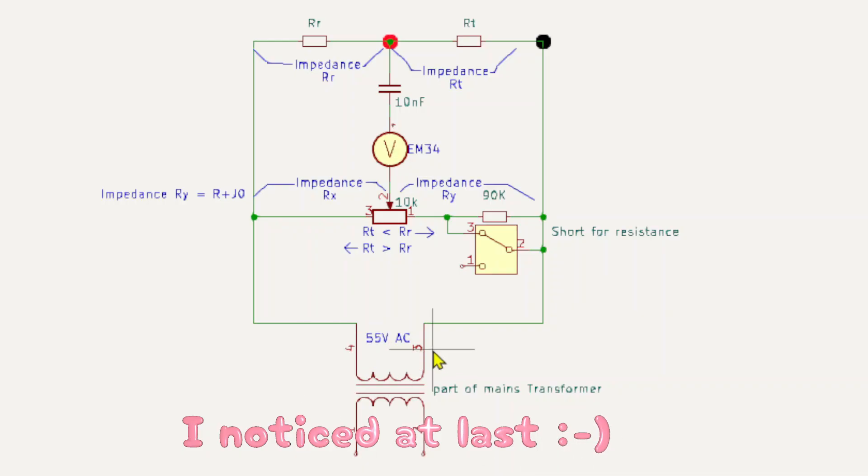It's got an AC supply, and so as the measurements are in AC, technically we're measuring impedances and not resistances. But the resistor on test and all the resistors in here will effectively have some form of capacitance or inductive parts. But at 50 hertz the inductance from the leads and capacitances from across the leads are going to be so negligible we won't even think about them.